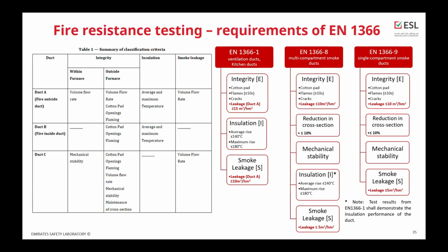What you can see is that EN provides an additional type of duct, which is duct C. This duct type C represents smoke extraction duct, which is tested either as per part 8 or part 9, depending on the end-use application. What is also very important for you as a manufacturer is that the EN standard focuses very much on the leakage of these ducts, because leakage is not only a separate classification which you can get or don't need to, but is also used to assess integrity. If you exceed a certain limit of leakage, you fail the integrity, which means the whole duct fails the test.